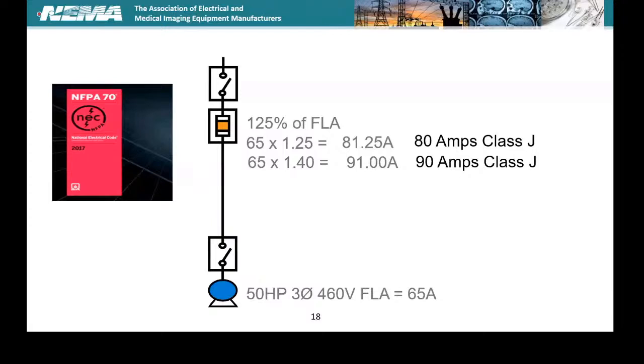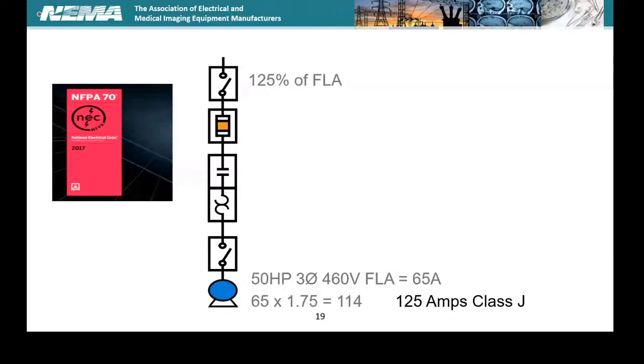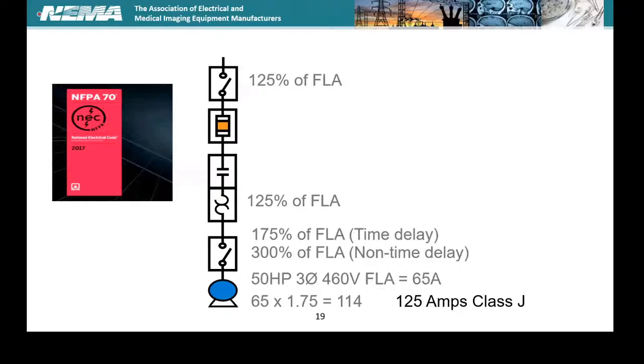So where's my slide? I lost my slide. No, we'll go back to it. So here is one. Now we've got just short circuit protection. We have a 50 horsepower motor with 65 amp full load amperes. And we go 1.75, which gives us 114 amps. Now we can go up to that next size up, that 125 amp Class J fuse, for our short circuit protection.